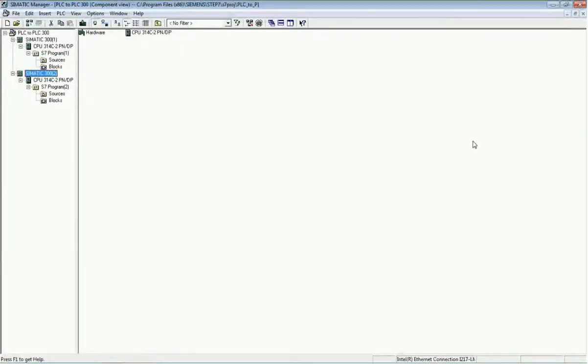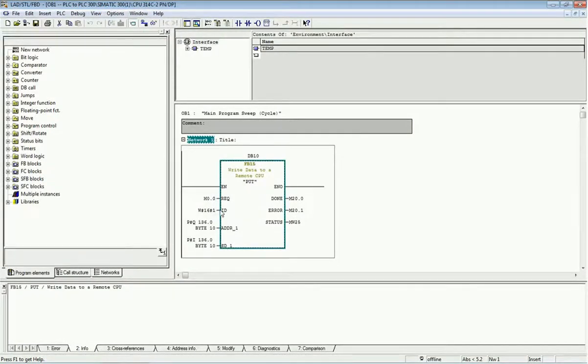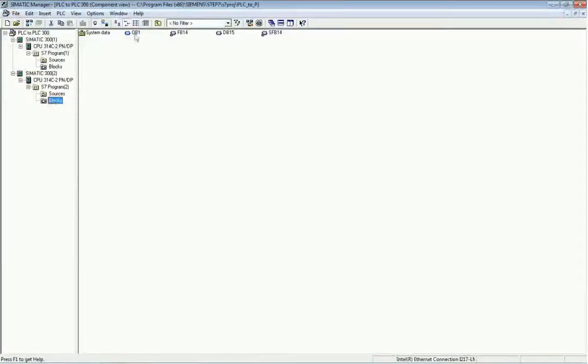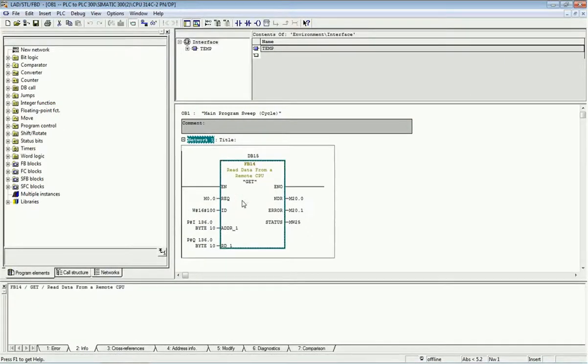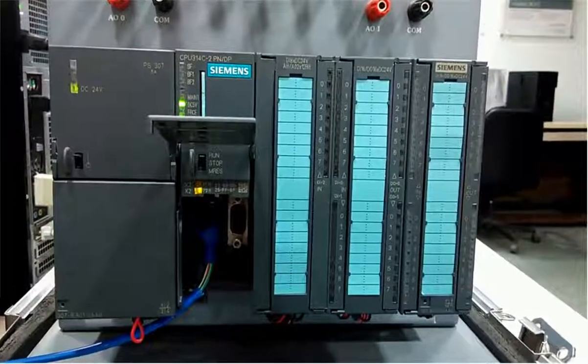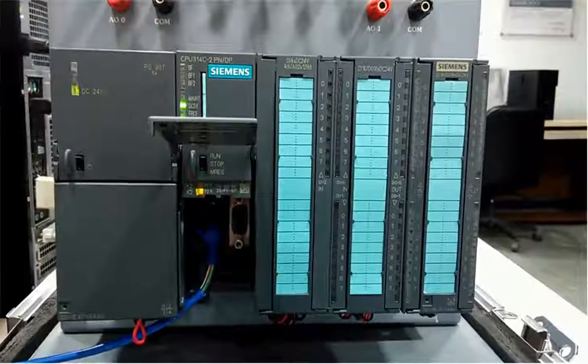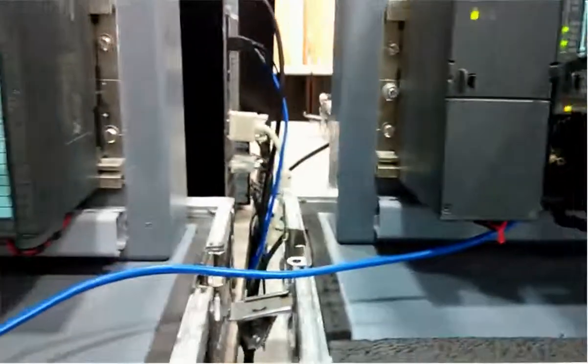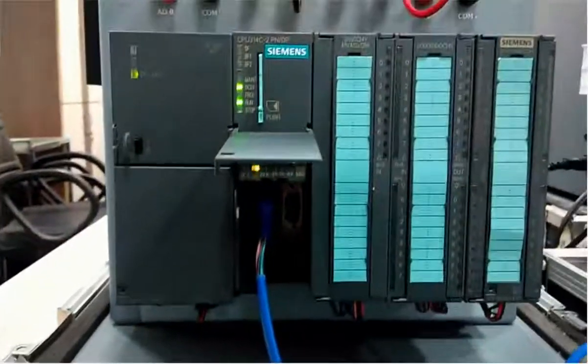Now we will see physically how the two PLCs communicate. In the first PLC we used the PUT block, so from this PLC we send the data. From the second PLC we receive the data — this is one-way communication. If you want two-way communication you can add both GET and PUT blocks in both PLCs for bidirectional communication. Here we have the physical Siemens S7-300 PLC — this is the first PLC with the PUT instruction downloaded, connected to the second PLC via PROFINET or Industrial Ethernet cable.